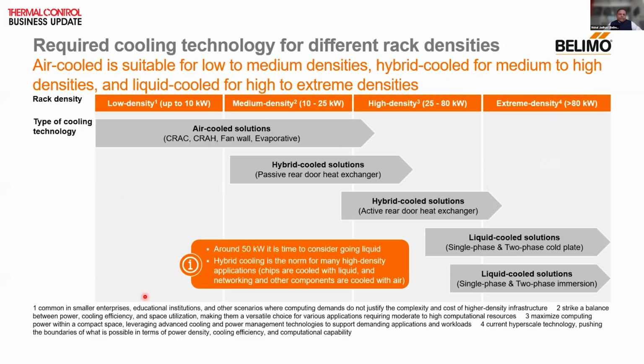This is another representation I tried to put together, about low density up to 10 kilowatts. Up to 25 kilowatts, we can have a combination of air cooled servers and hybrid cooled servers. But when it comes to density of more than 25 kilowatts, or let's say more than 80 kilowatts, liquid cooling, be it single phase, two phase, immersion cooling, rear door heat exchanger, or direct to chip cooling, whichever method we talk about, has its application where the rack density goes up. And if you recollect my presentation at the beginning, we saw some key elements of why this need will go forward.